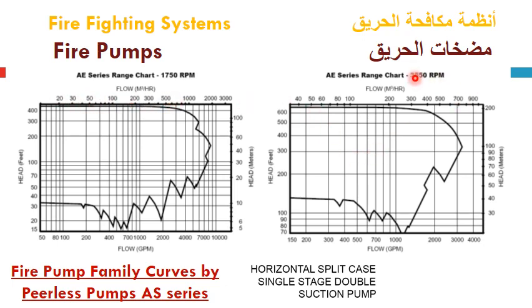The same graph but for 3550 RPM for one pair of pole motor with 60 Hz. However, it will give 2950 RPM with 50 Hz as here in Egypt. Both sides of head in feet and in meter are the same, similar to the first curve, and the flow in GPM and meter cube per hour.